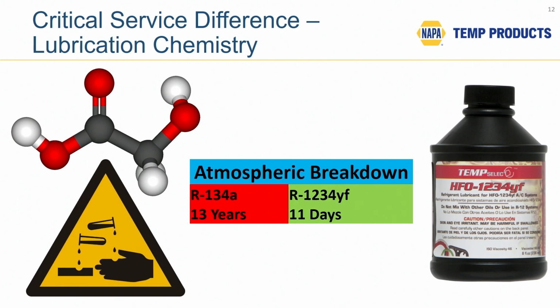because you've got rapid acid buildup in the system, corrosion, and next thing you know, you've got a leak in the condenser or the evaporator or something like that. So this is why it's very important to do a deep evacuation to get all the air and moisture out of an R1234YF system.